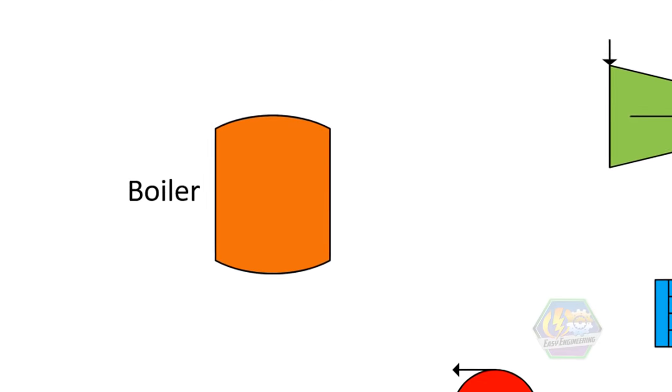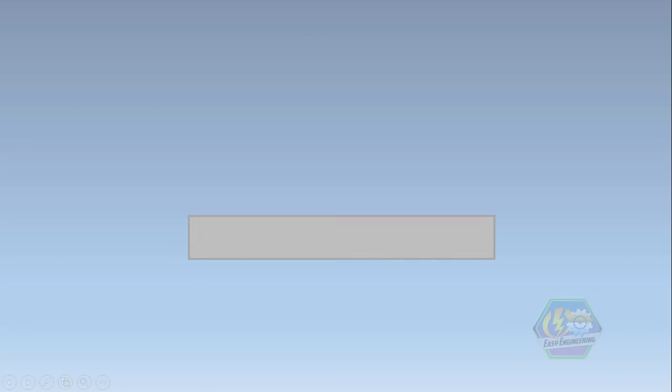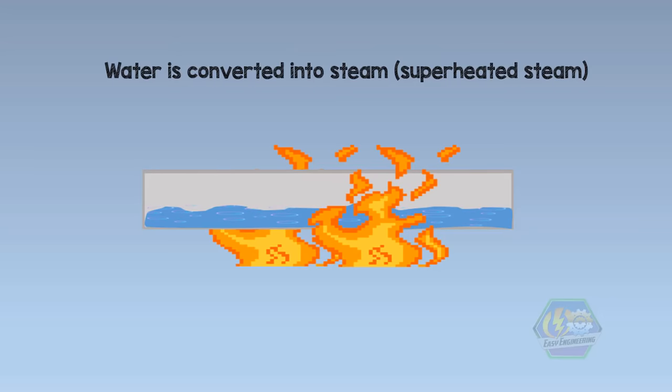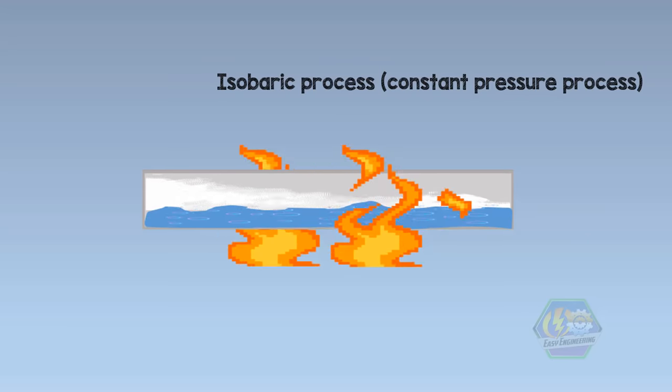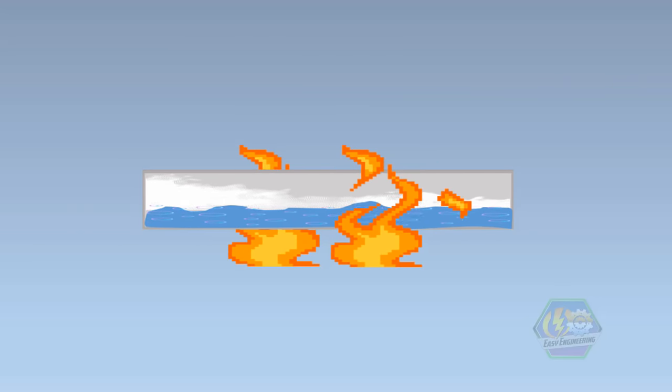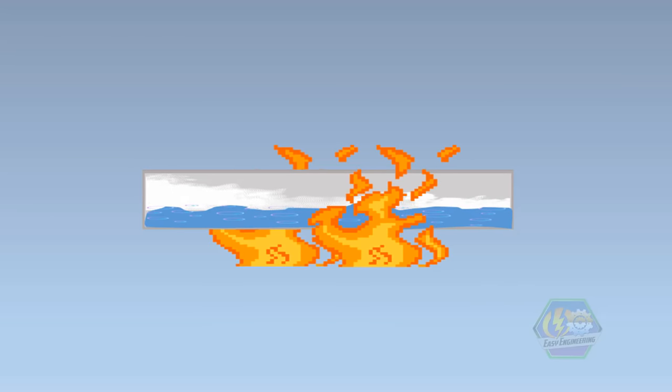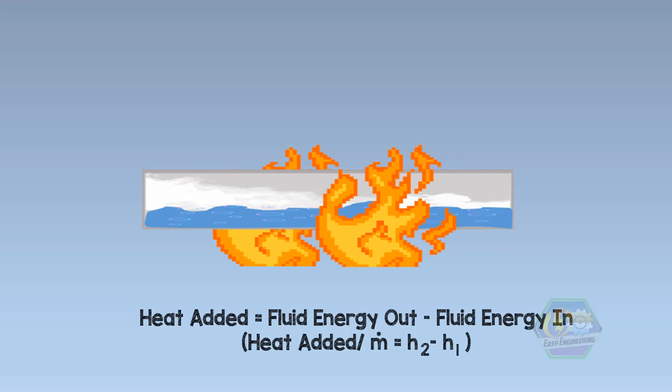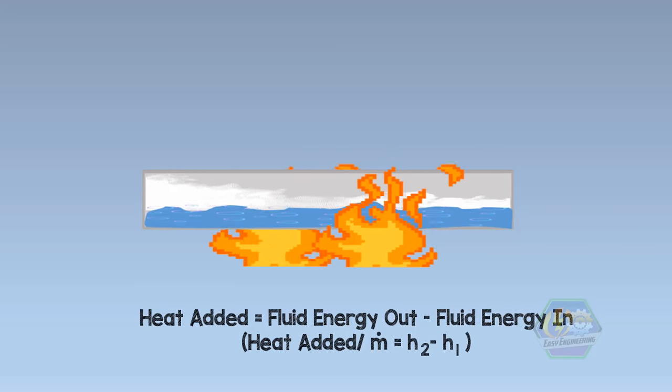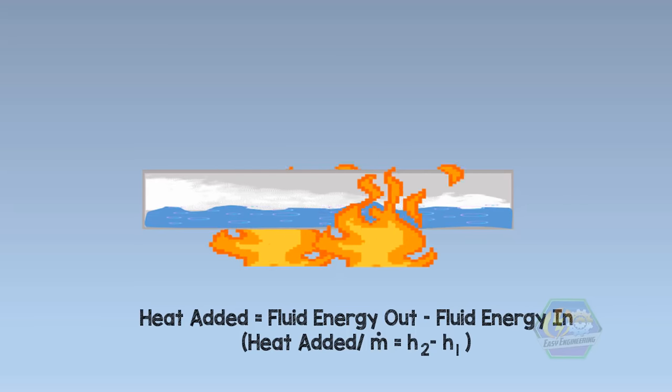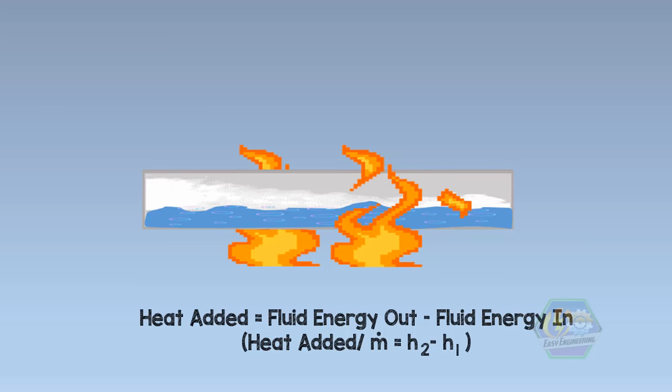For process 1 to 2 boiler, these are the things that we need to remember. Since boiler is a heat exchanger equipment, heat is added into the boiler through a fuel, which may be coal, oil, or natural gas. Here, water is converted into steam or superheated steam. This is an isobaric process or a constant pressure process. The temperature and entropy for this process increases. And we can solve the heat addition by using the formula: heat added equals fluid energy out minus fluid energy in, or enthalpy out minus enthalpy in for the boiler. Note that this equation is formed by using a mass and energy rate balance for a controlled volume at steady state, neglecting pressure drop. So, those are the important things that we should remember with understanding the boiler process.